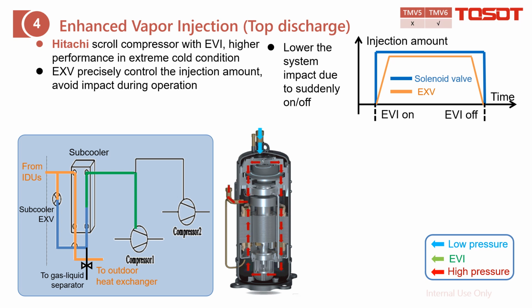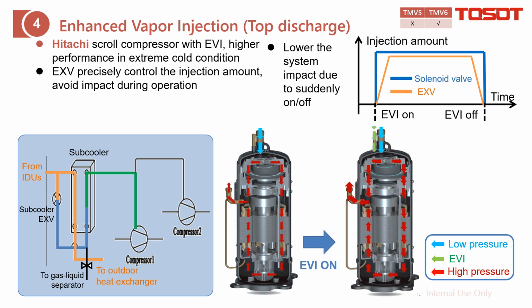Similar to the EVI of top discharge, this time the diagram is almost the same, but the compressor is from Hitachi, it is scroll, and here is the EVI off. And when we turn on the EVI, we get another inlet from here, then we can have a higher refrigerant flow rate to increase the capacity in low temperature heating. And also we apply EXV instead of the solenoid valve, and also there are two EXV even for a single compressor.